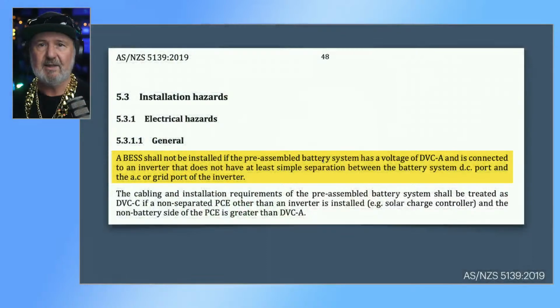So, just to reinforce this from the battery standards perspective, because we've been talking about the inverter standard and the PV array standard, the battery standard 5139 makes it very clear that a BESS, now this, of course, the sections 4, 5, and 6, but they all reflect the same wording, except 4. Section 4 is for a pre-assembled integrated BESS with basically inverter and battery integrated into it. So I should bring up that slide so you can actually see what I'm talking about. An integrated BESS is a Section 4 solution, and this doesn't apply.